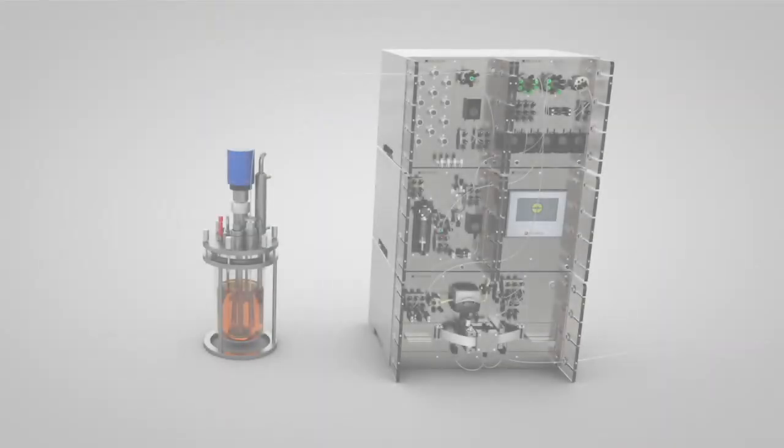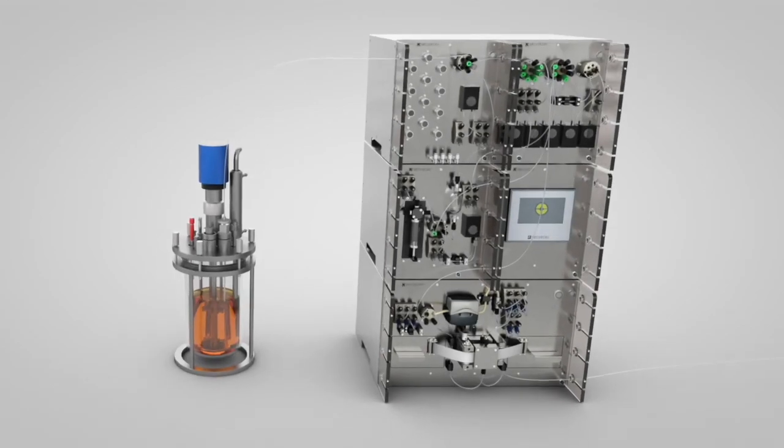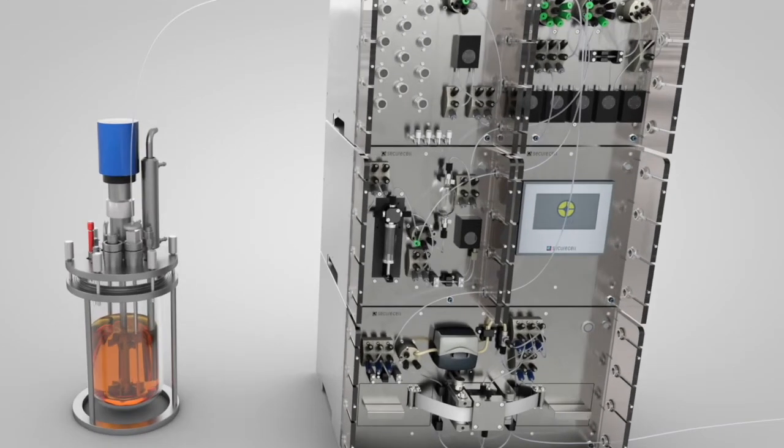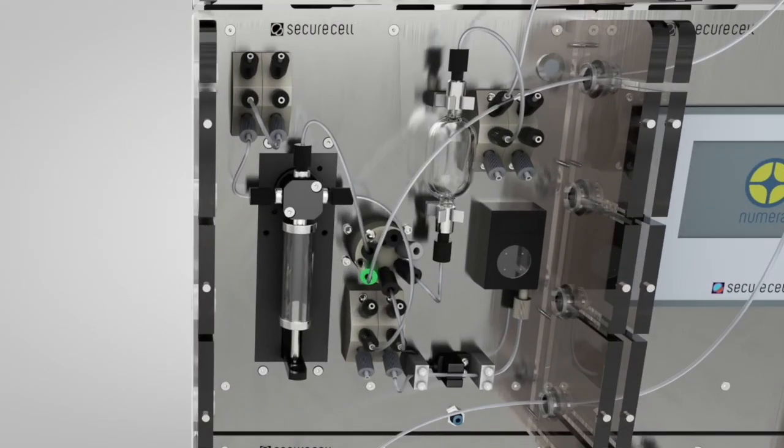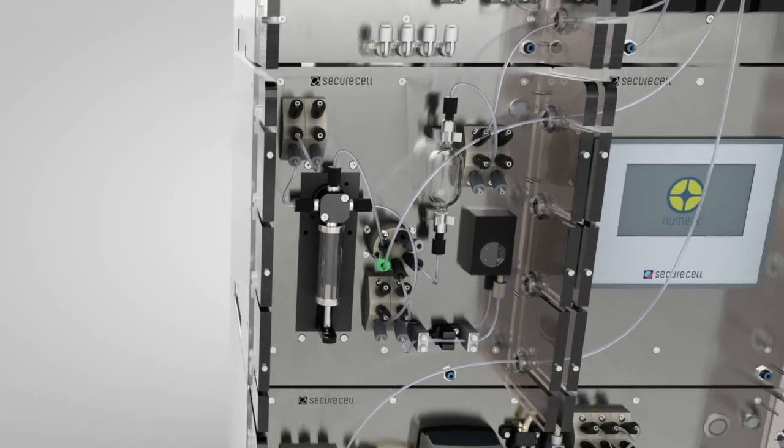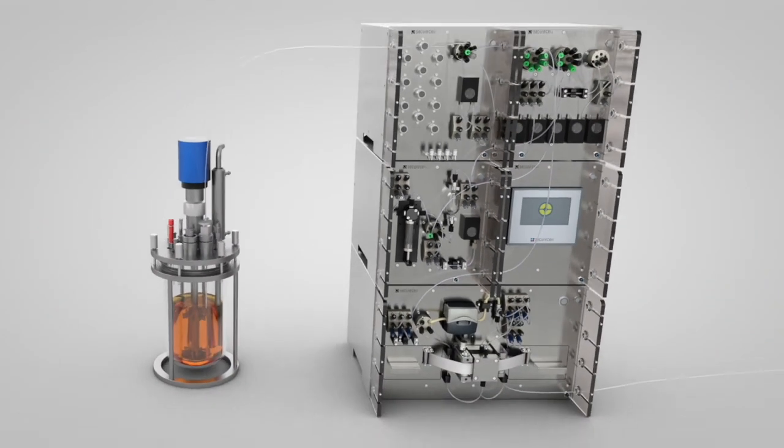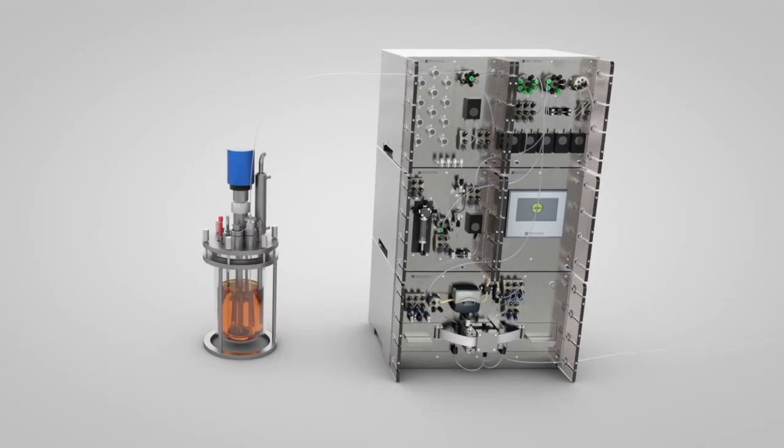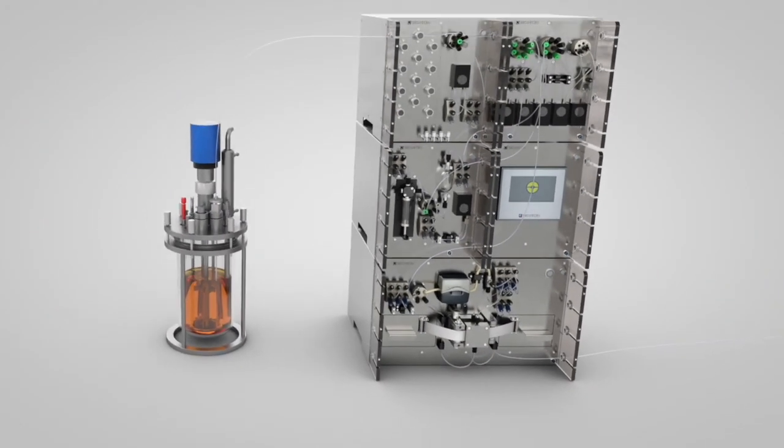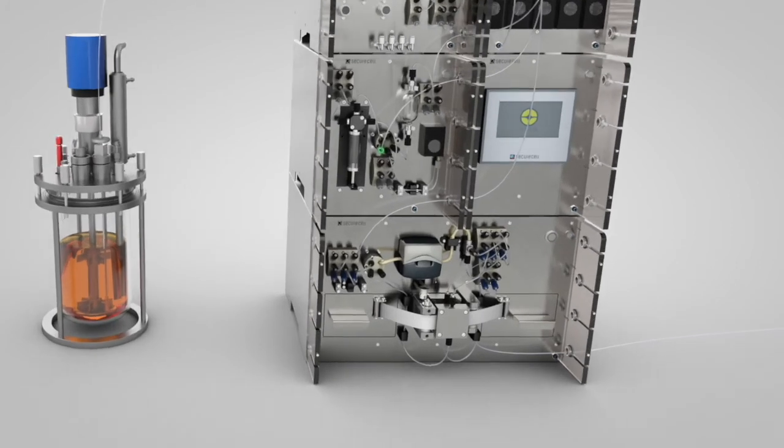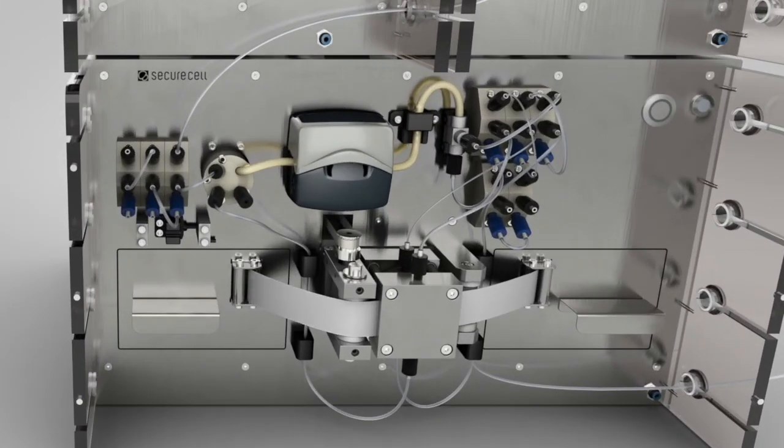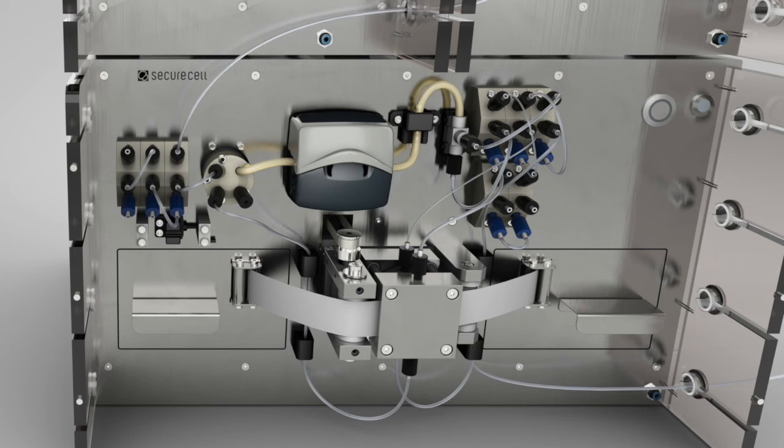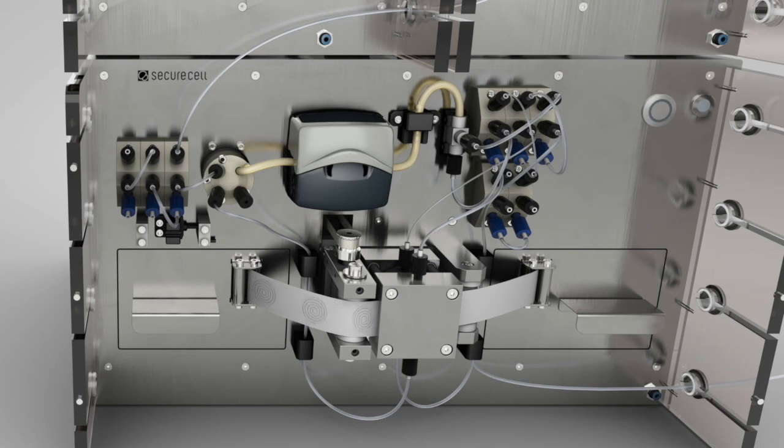Numera's dilution module allows you to dilute your sample with the desired solution and transfer it to a cell counter or analyzer in an automated manner to be quickly analyzed. Numera's tangential flow filtration module allows reliable cell removal and at the same time strictly avoids clogging and cross-contamination. The unique low-maintenance tape filtration technology applies a new piece of filter for every sample.